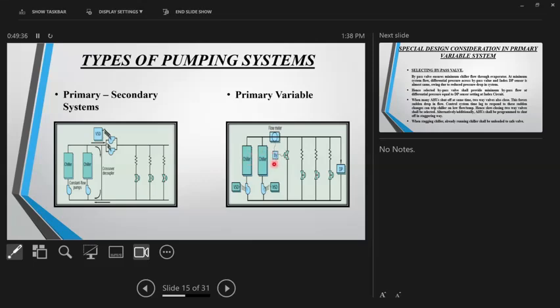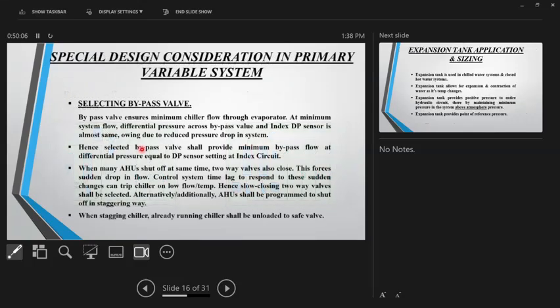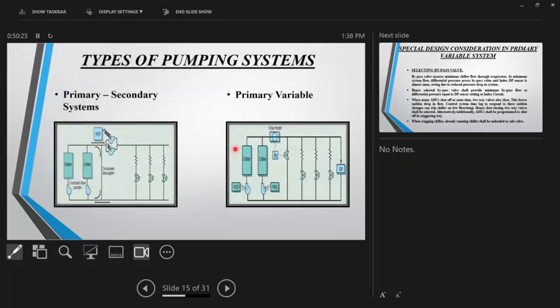Let's say a chiller system cannot go below 100 GPM. So 100 GPM is the minimum you can get from this circuit. And at that time, my minimum load in the night wants only 60 GPM, for example. So the chiller can give you no less than 100. Your requirement was 60, so the remaining 40 would go from here. So the pressure drop across this valve at 40 GPM should be equal to delta P setting. Simple. This is the sentence: selected bypass valve shall provide minimum bypass flow at differential pressure equal to DP setting at index circuit. If you could do that, in other words, you are selecting a valve with 100% authority. And authority is nothing but the ability to control the flow variations without hunting too much.